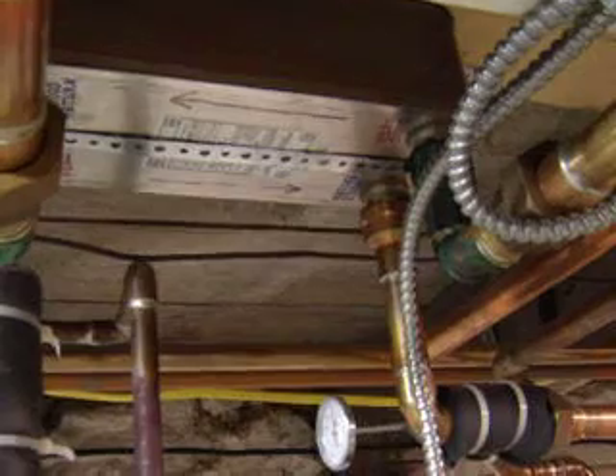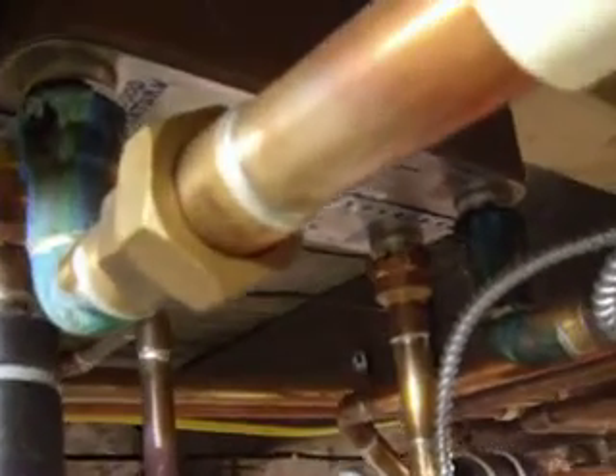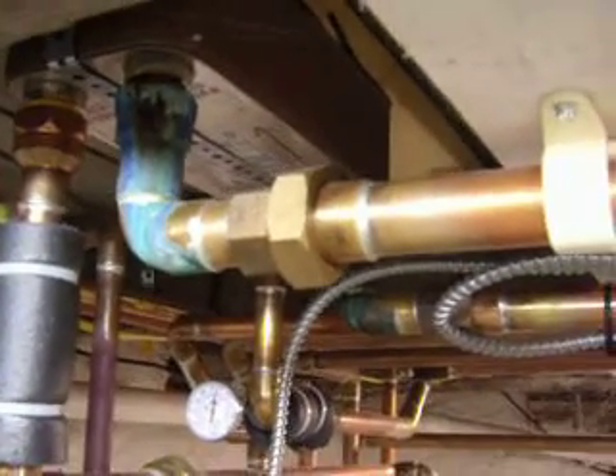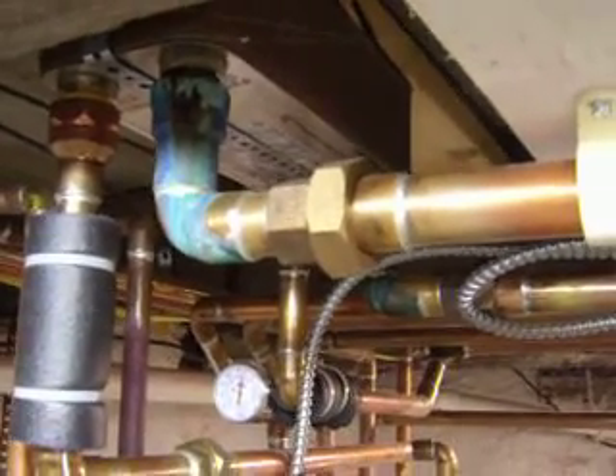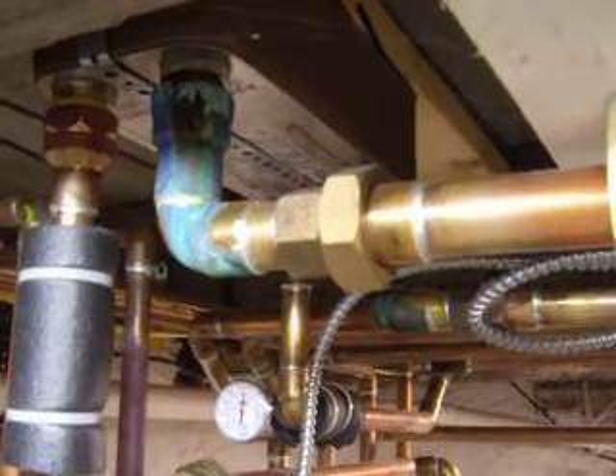The reason I'm running a heat exchanger is because the Greenwood boiler out in the garage is filled with glycol antifreeze. In case I opt to shut the system down in the winter, I can close things off and I don't have to worry about anything freezing up if we opt to go away for a winter vacation. But anyway, 30 plate exchanger. Got the in-feed side coming in there, it runs out.